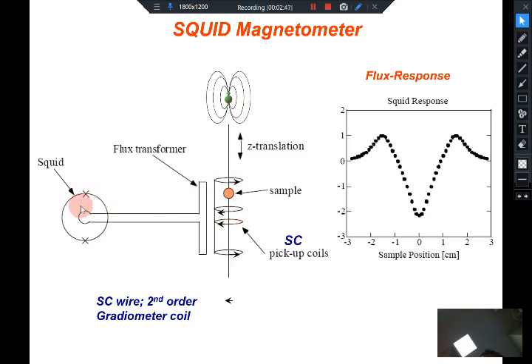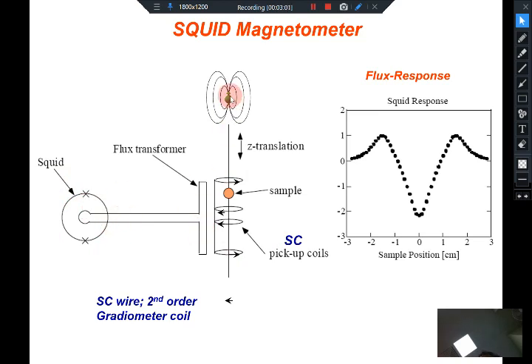The SQUID magnetometer — the SQUID loop — you do not actually take the sample and put it directly on the SQUID loop. The SQUID loop is actually kept far away from this pickup coil and is placed in a magnetically shielded region. The reason for that is that this coil can be introduced in a larger magnet, so that you can study how the magnetization of this sample changes as a function of applied magnetic field, and this applied magnetic field should not affect the SQUID sensor.